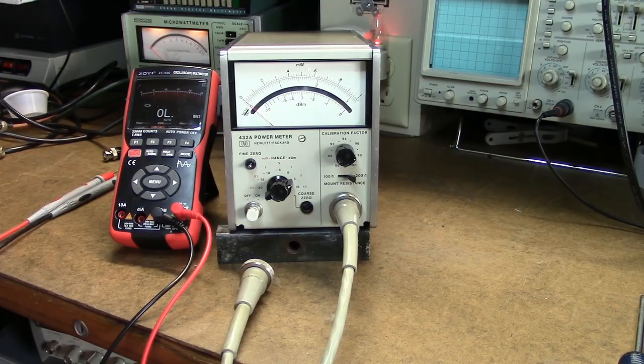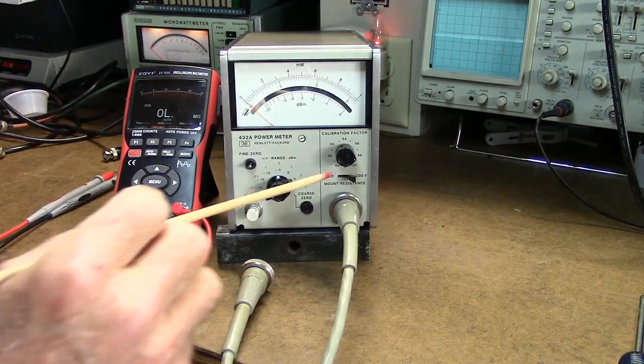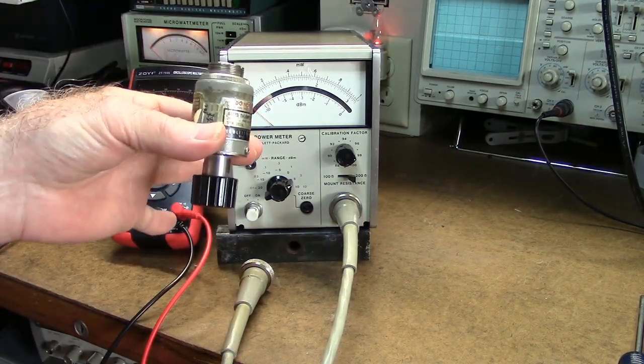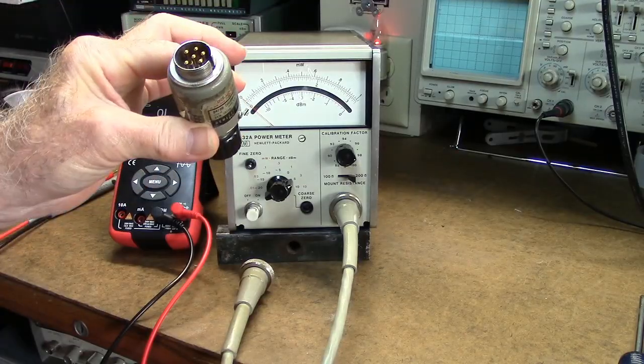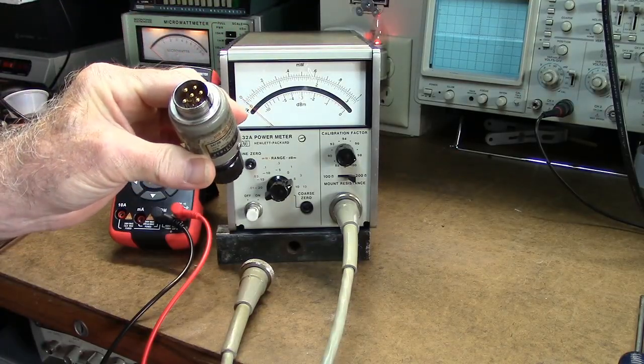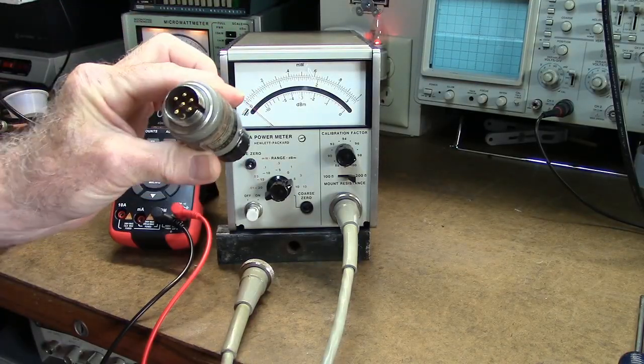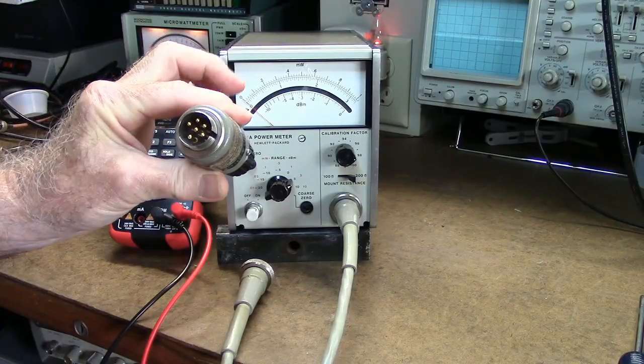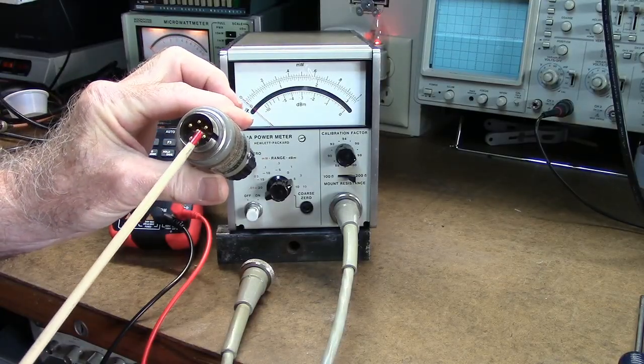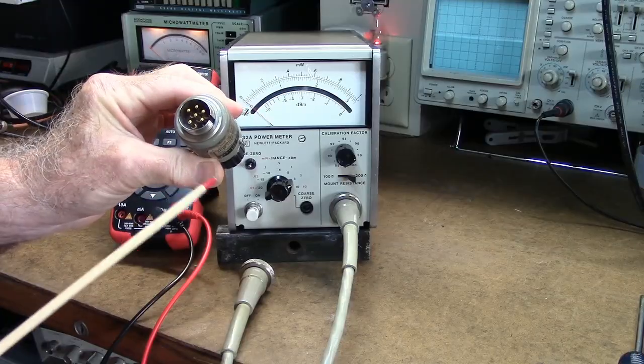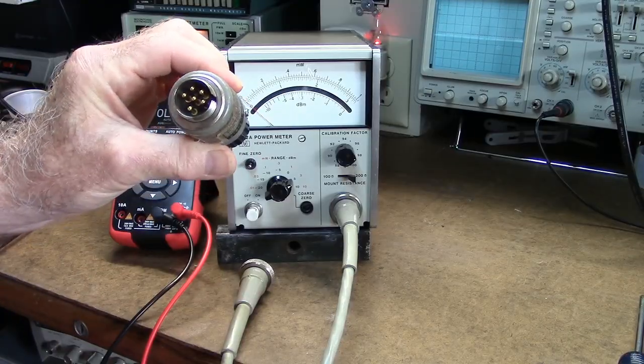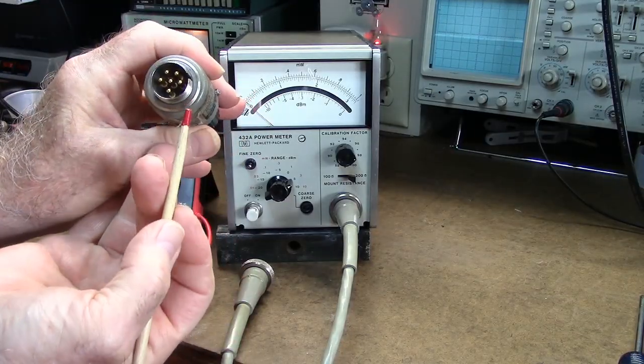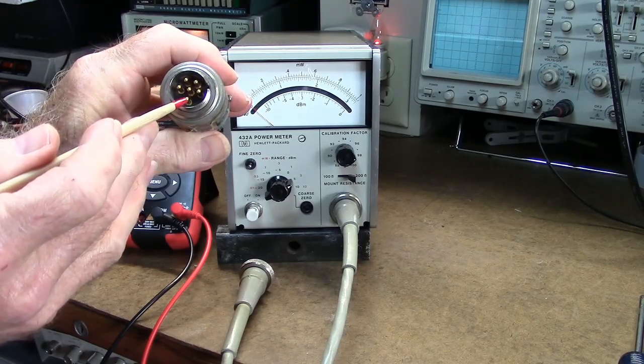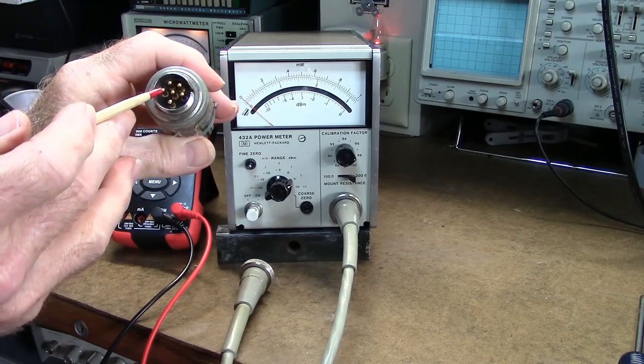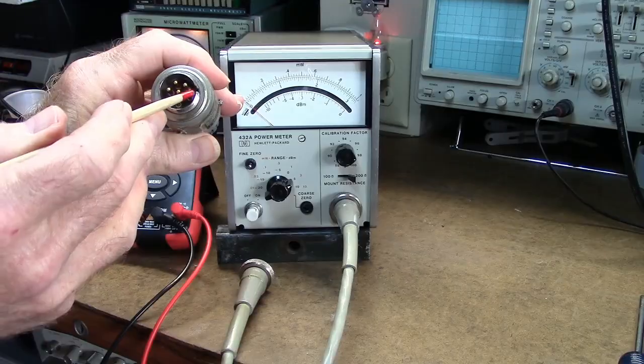Now if you find one of these at a Hamfest, of course like I say, try to get it with the cable and the thermistor mount. But something else you probably should do is try to find out if the thermistors have been blown inside of the head here. There's two thermistors. And if you look at this bottom here, the pin arrangement, this is pin 3 and this is pin 4. And this is pin 1 and pin 2.